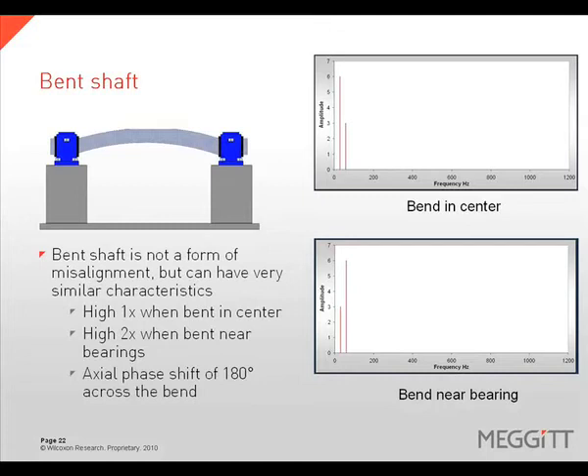A bent shaft can exhibit either a high 1 times or a high 2 times depending on the location of the bend relative to the support structure. If the bend is close to one of the supports or bearings, 2 times vibration will likely be dominant. If the bend is farther away or centered between supports, 1 times rotational speed will likely be predominant. With misalignment the phase shift occurs across the coupling, while with a bent shaft the phase shift occurs across the bent portion, with a 180 degree phase shift expected in the axial direction.